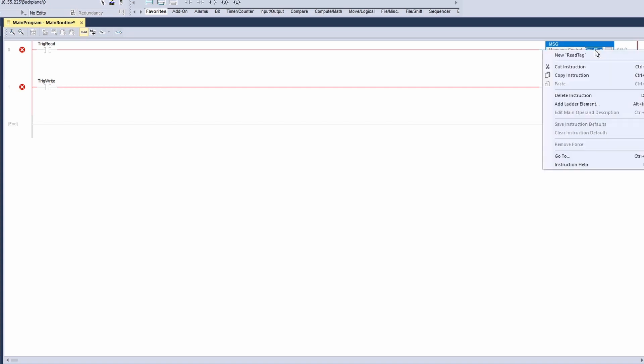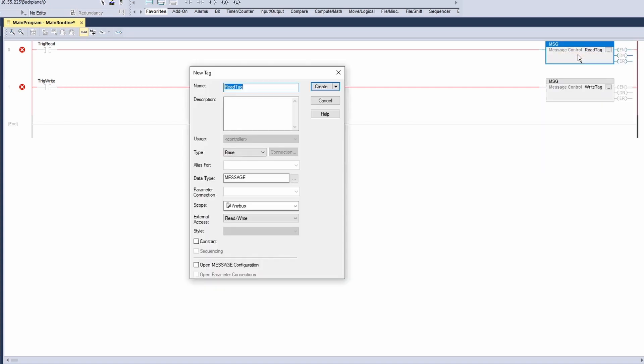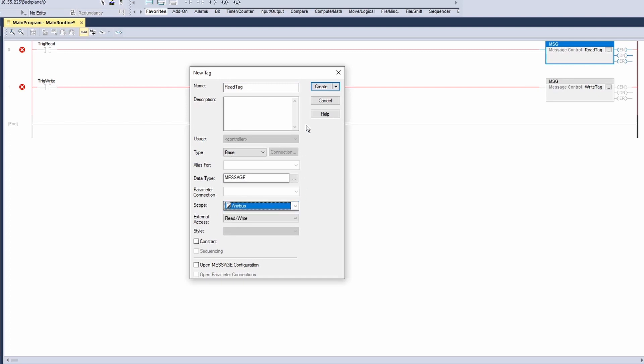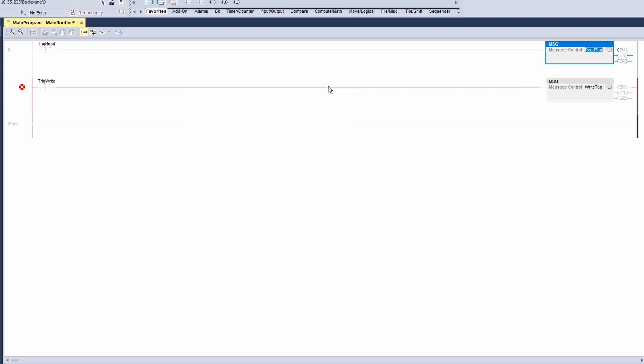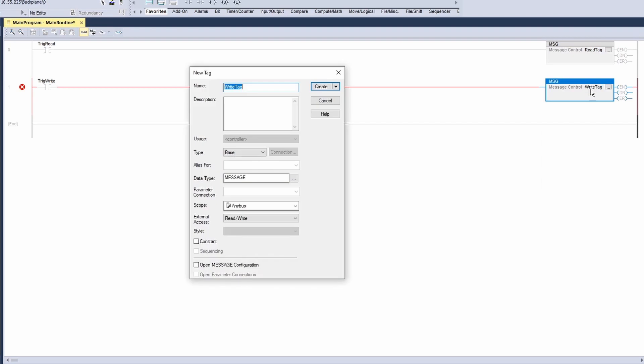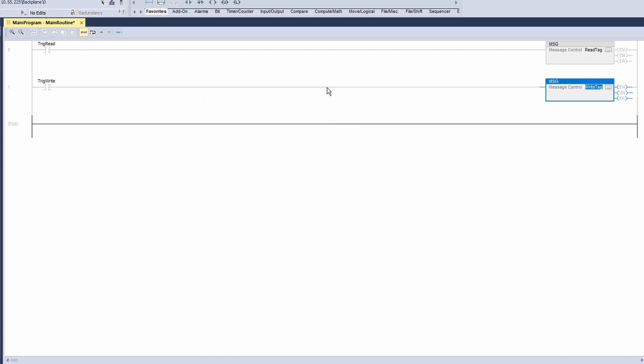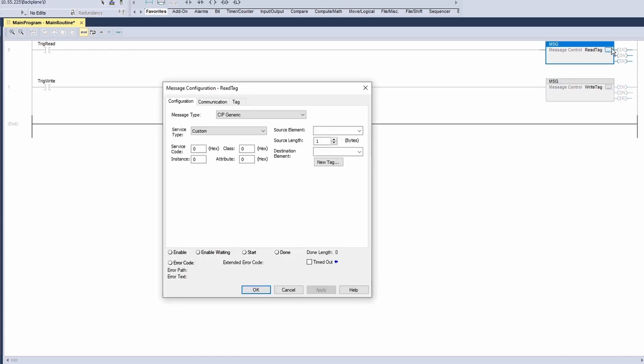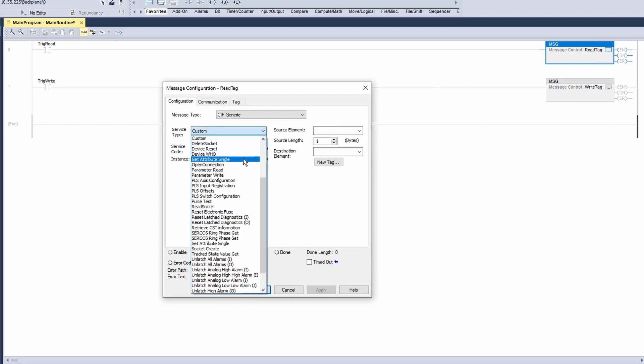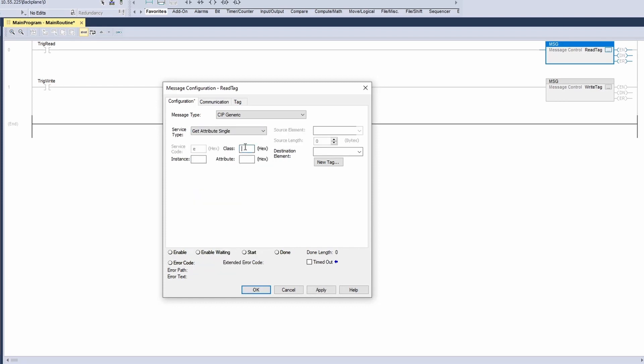Name the message elements read tag and write tag. Right-click the read tag and click new tag to add it as a tag. Make sure the scope is Anybus, then click create to create the tag. Set the service type of the instruction to get attribute single. Enter class 4, instance 100, attribute 3.